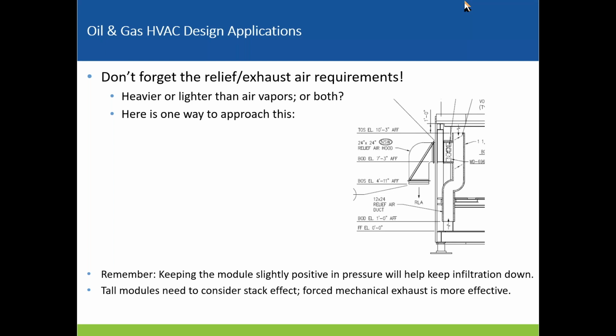20 feet, sorry. We did some work on that a few years ago where the lower reliefs became intakes, bringing all the outside air in and everything was exhausting out the top. We ended up having to swap those out for mechanical exhaust fans, which sounds easy, but it's not really with all the oil and gas effects. Better design it right the first time. I do recommend keeping the module slightly positive in pressure just to keep infiltration down, even if it is a process module, depending on how close it is to any other spaces. So if it is actually attached to another space, you may not be able to.